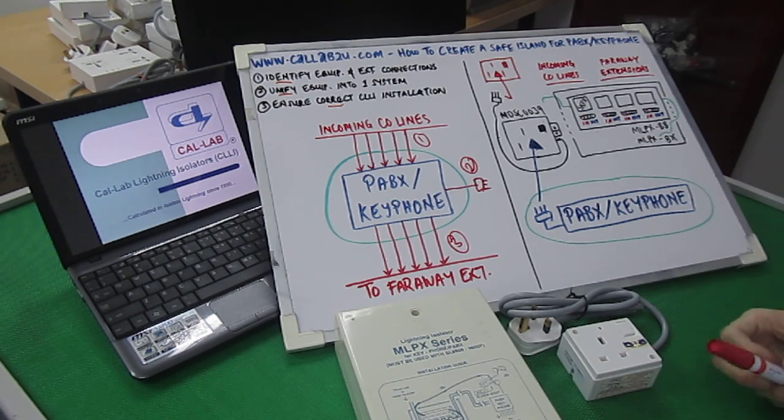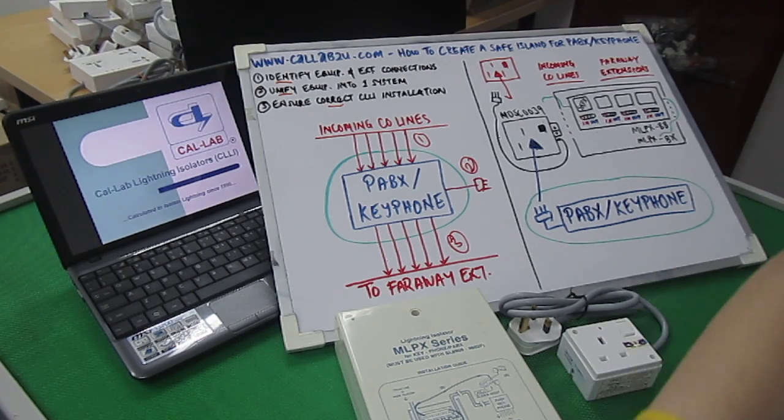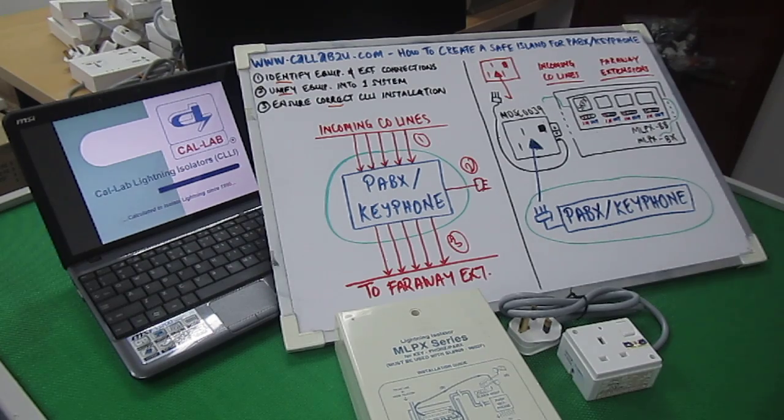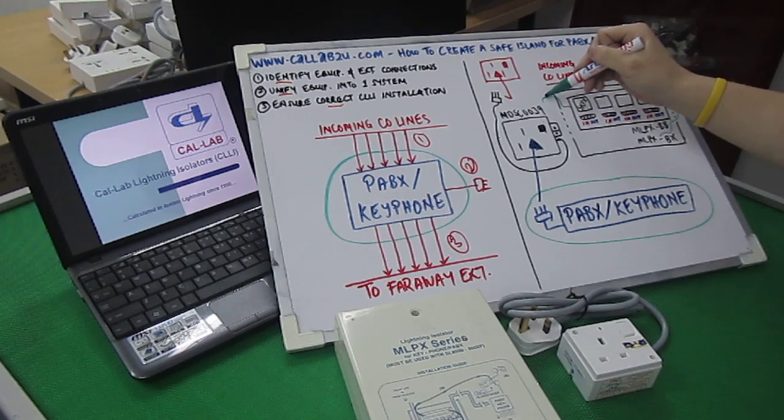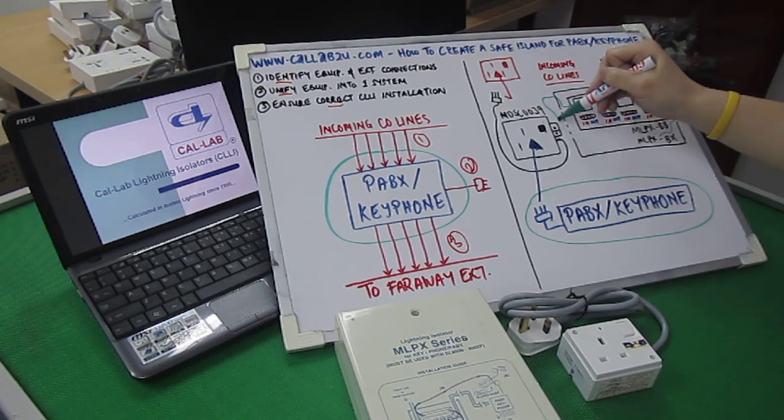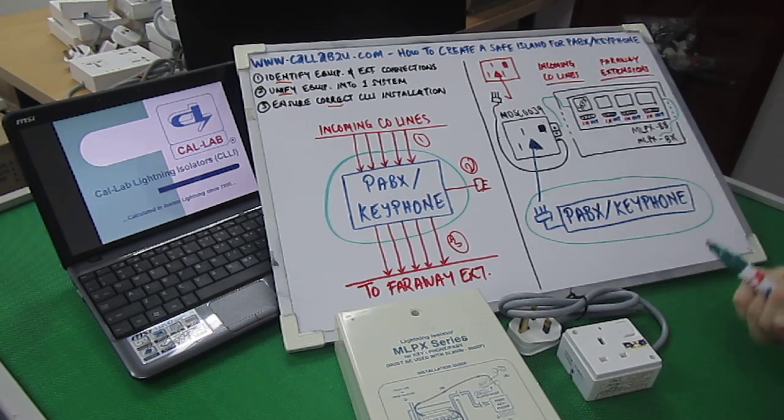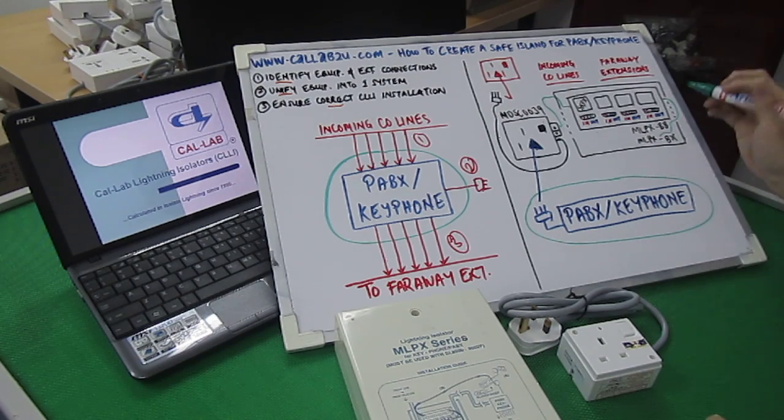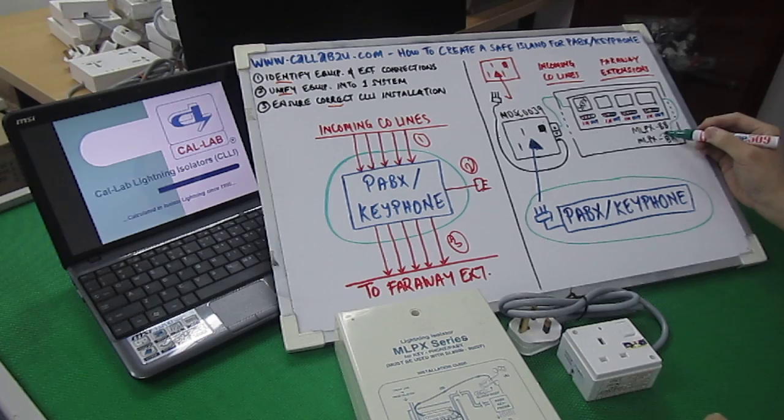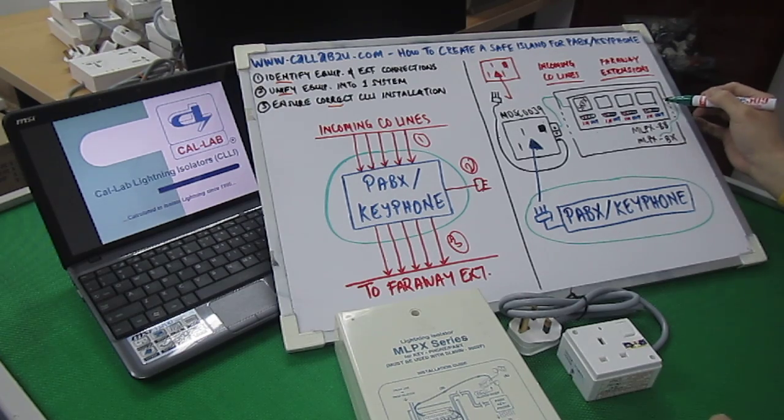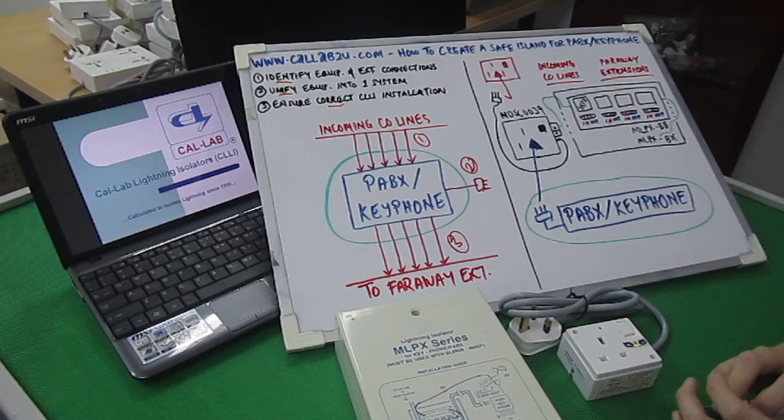The third thing to note is that all CalLab Lightning Isolator's green wire or earth wires need to be connected back to the main power isolator. So, as you can see, the green wires here need to be connected back to the earth terminal of the MDSC0039. You'll note that there'll be another one hanging by the side here. Now, this is to actually connect to another baseboard in the case you have additional incoming or extension lines.